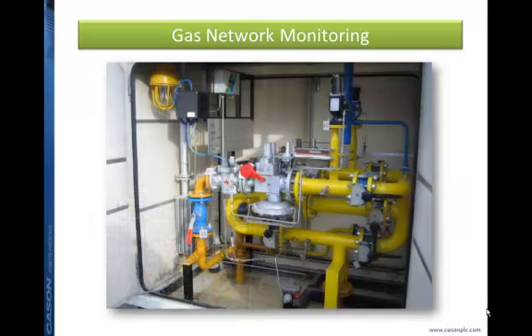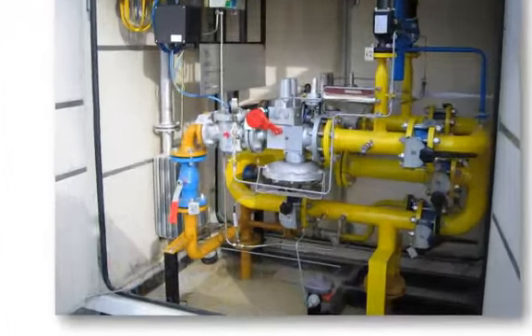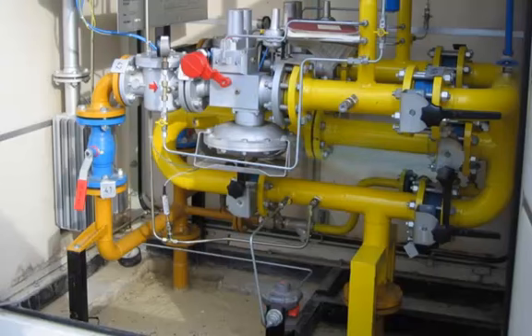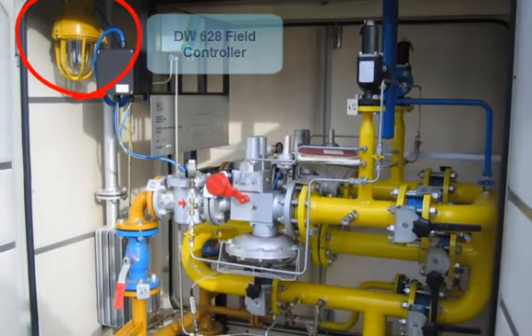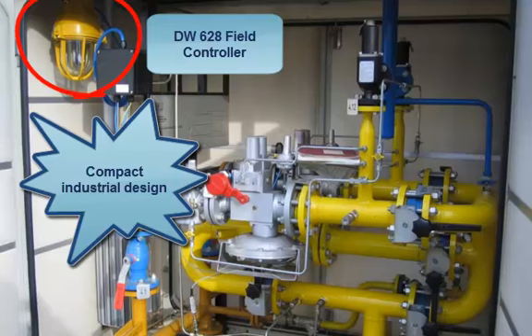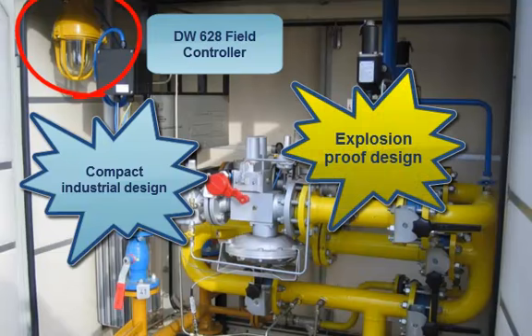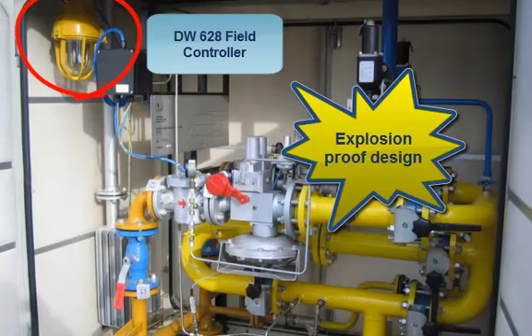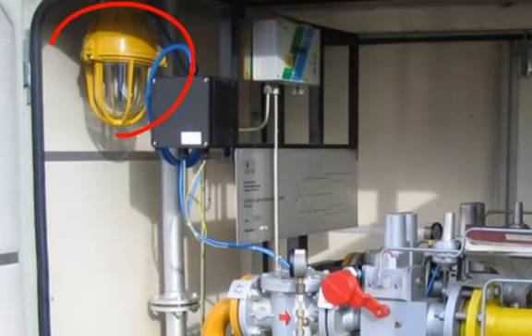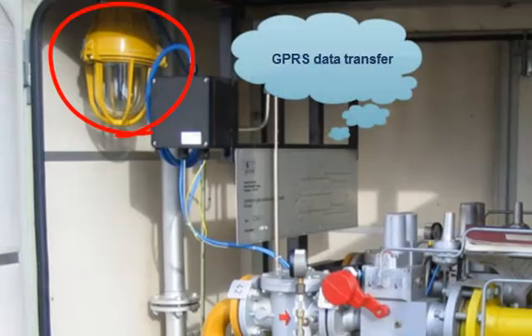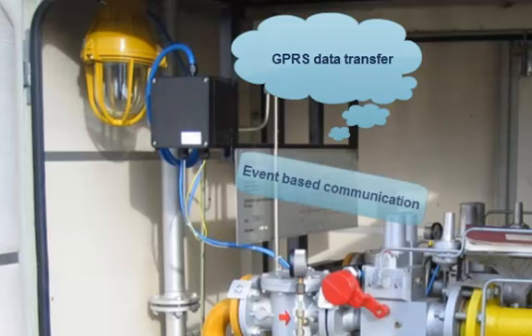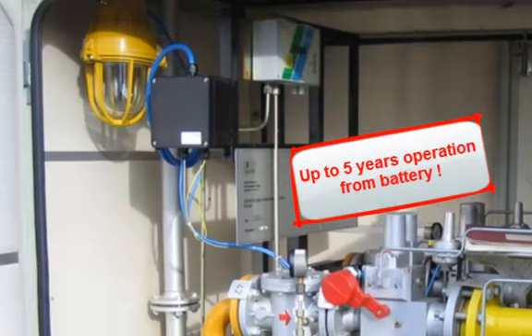The gas flow from the transportation pipeline comes from under the ground. This is a common facility with two rails. There are filters and two pressure regulators with pilot valves. That DIWICON field controller device is quite unique. It has explosion-proof design and uses its built-in batteries, not just for operating, but even for supplying the connected field sensors. In addition, all the collected data is transferred to the central database by using built-in GPRS communication. And by the way, thanks to the optimized event-based communication, the internal power supply allows independent functioning of up to 5 years, depending on the application, of course.